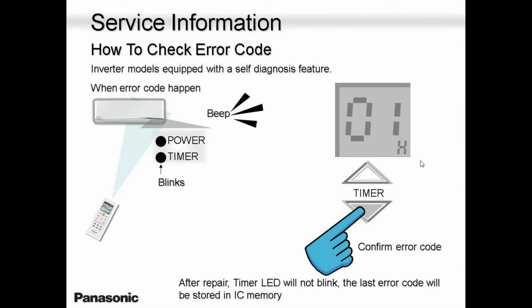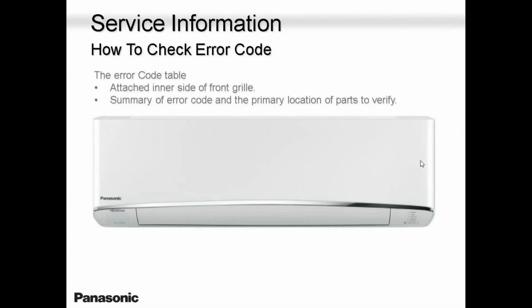2 dashes, okay? You will see 2 dashes. And when you see 2 dashes, now you are already in the failure recall mode. So now you want to find out what the error code is. You will use the timer up and down, okay? Not the temperature. Remember, not the temperature up and down. The timer up and down. You will scroll through all the error codes. You will scroll, you will scroll, you will scroll.